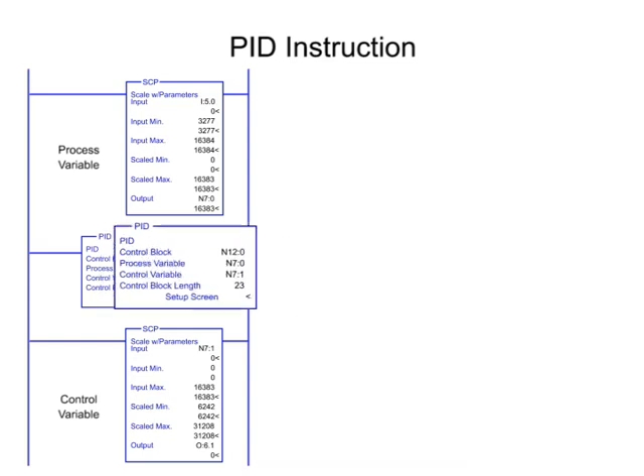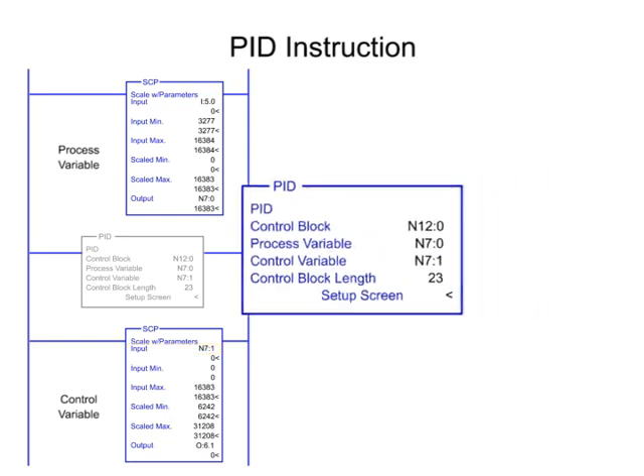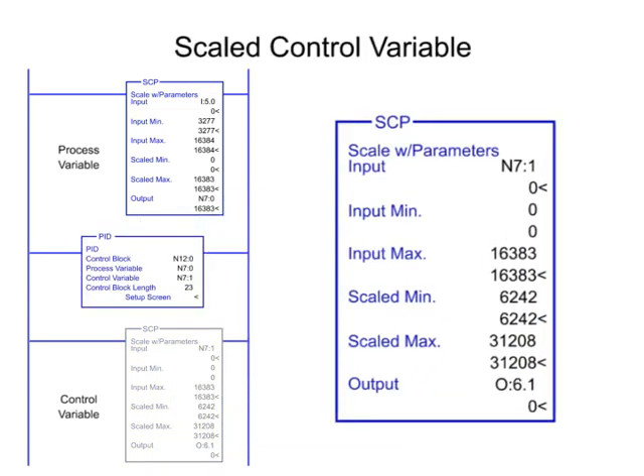In the PID instruction, the process variable parameter is programmed as an integer file, which is the scaled value from the SCP instruction. The control variable parameter is programmed as an integer, which is the memory address for the output value. Next, the control variable range of 0 to 16,383 is scaled to an analog output module using the second Scale with Parameters instruction.